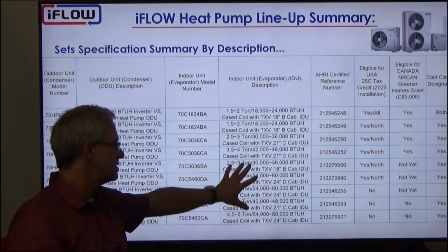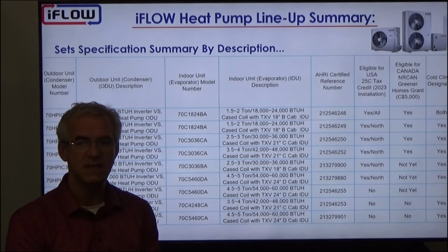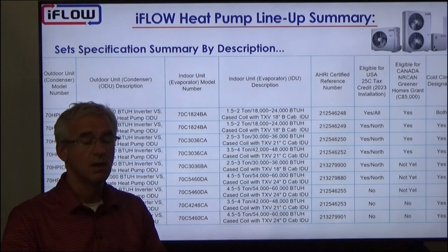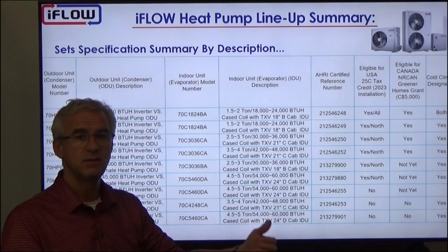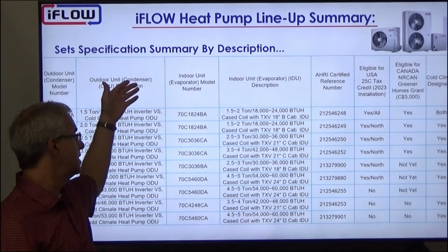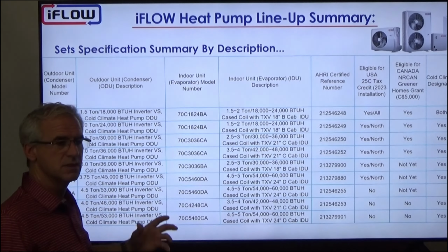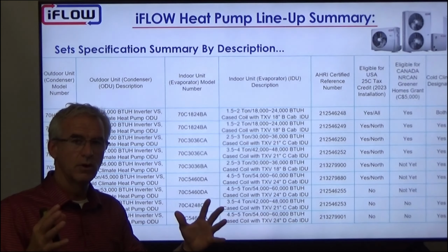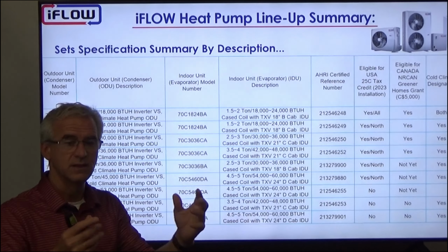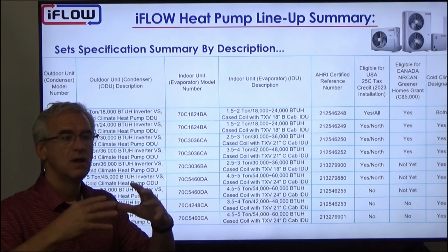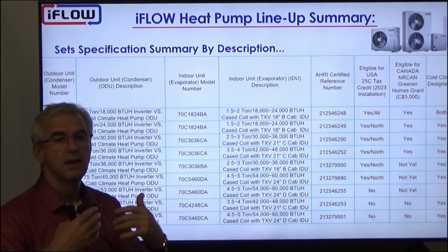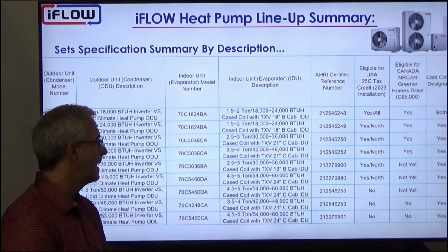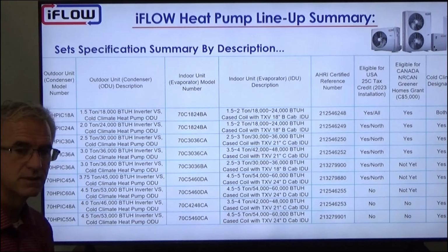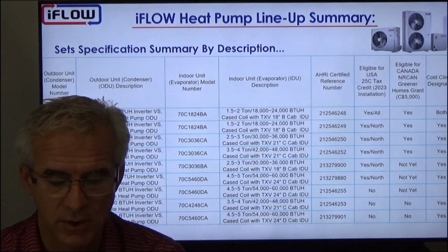You will notice as you look at them that oftentimes the evaporator coil is a little bit larger than the BTU load, or the BTU size, of the condenser. And that's because the larger the evaporator coil, the better performance we're getting. So it's a little bit bigger heat exchanger, a little bit more transfer area, a little bit better efficiency. And that's why they're a little bit larger than a typical system may be.